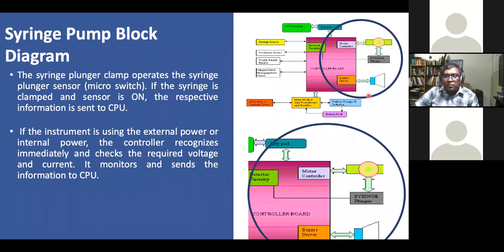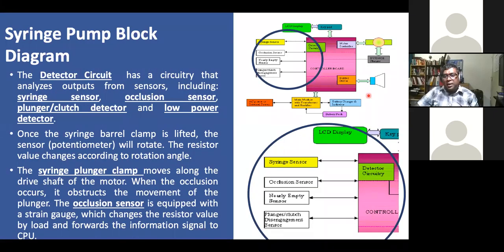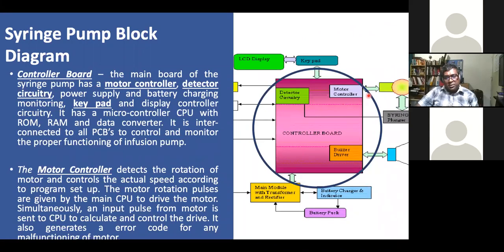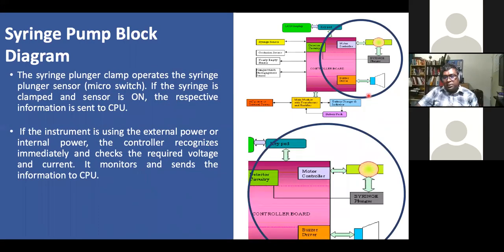So on the alarm part of it, the syringe plunger and clamp operate on the system that will indicate to the control. So the plunger sensor has a micro switch. If the syringe clamp sensor is on, the information will be sent to the CPU. If the instrument's external power or internal power control recognizes some difference in required voltage and current, it will send the information to the CPU as well. So all these are the key parts of it.